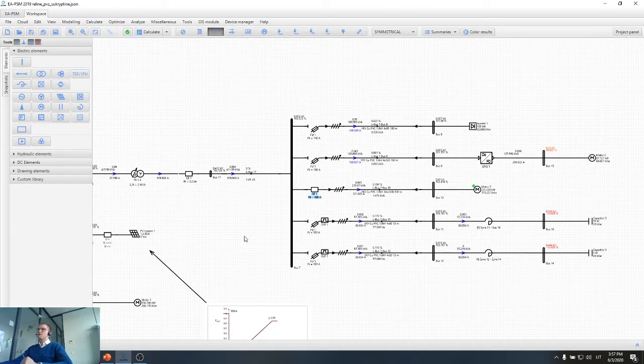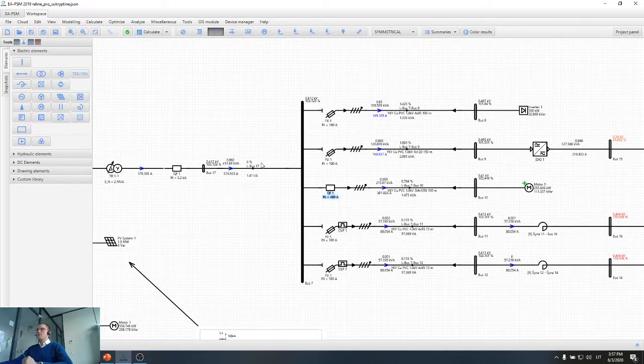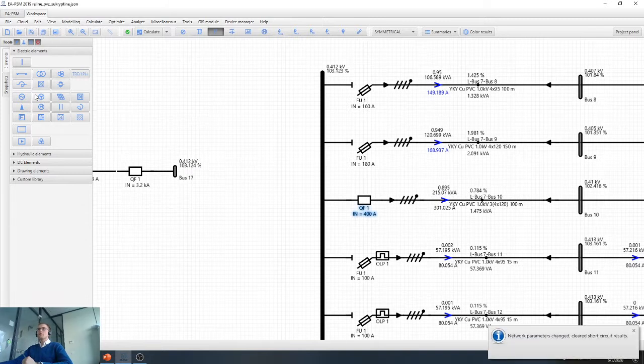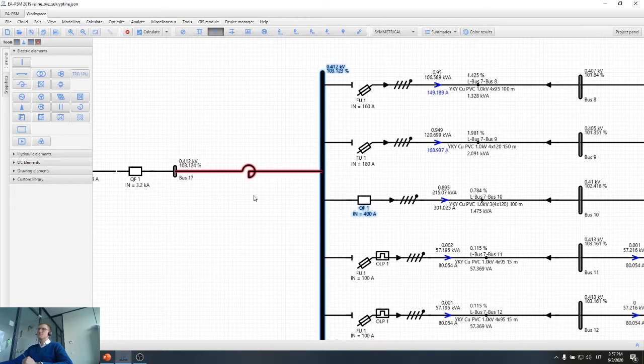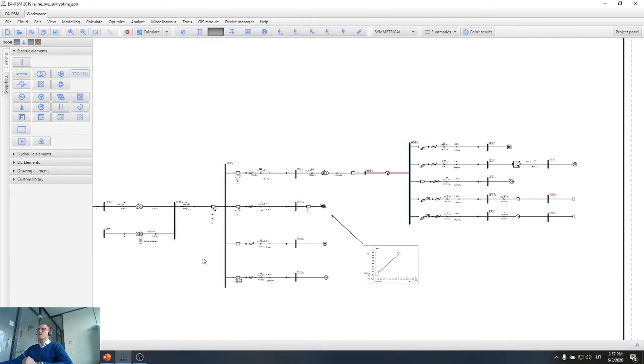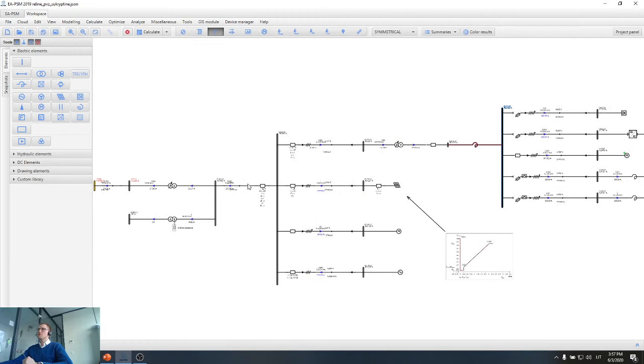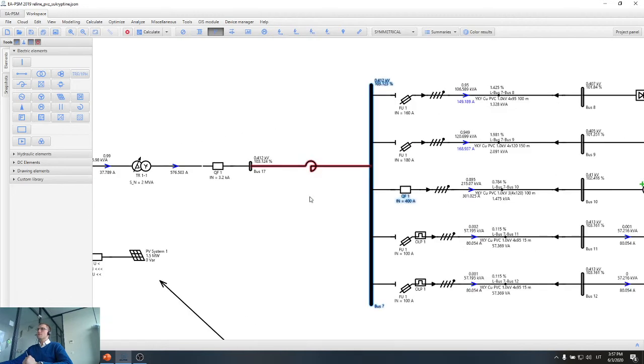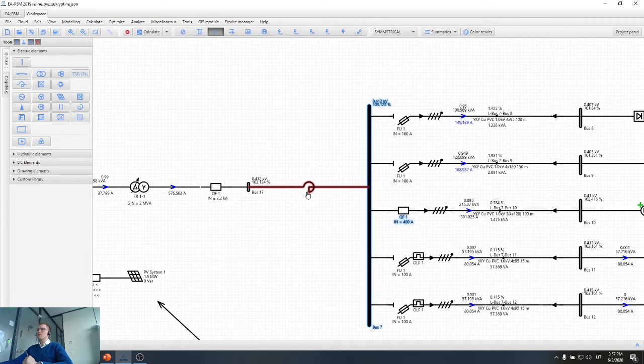It's very easy. We have to increase the impedance of the network actually. So instead of this line here, let me delete this line, I will add a series reactor. It is best to use a series reactor in the medium voltage side, because here we have smaller currents and this will cause smaller losses. However, just to give an example, I will connect this series reactor also in the low voltage side here.